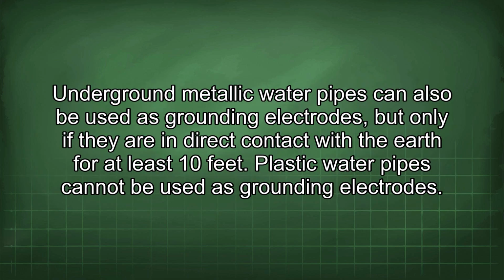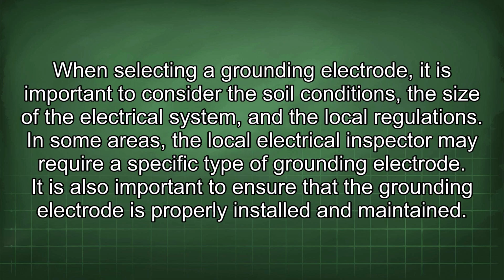Underground metallic water pipes can also be used as grounding electrodes, but only if they are in direct contact with the earth for at least 10 feet. Plastic water pipes cannot be used as grounding electrodes. When selecting a grounding electrode, it is important to consider the soil conditions, the size of the electrical system, and the local regulations. In some areas, the local electrical inspector may require a specific type of grounding electrode. It is also important to ensure that the grounding electrode is properly installed and maintained.